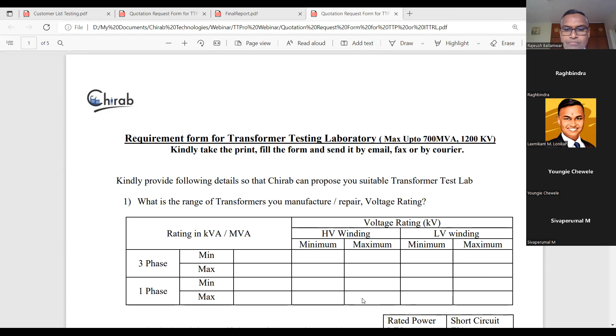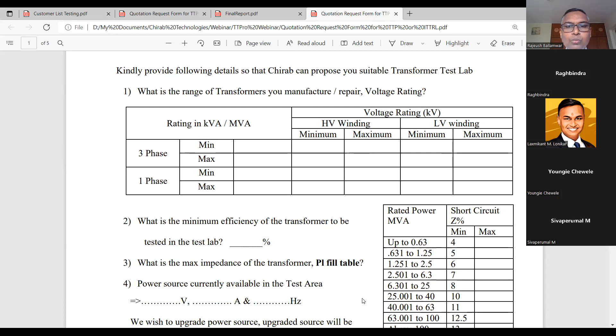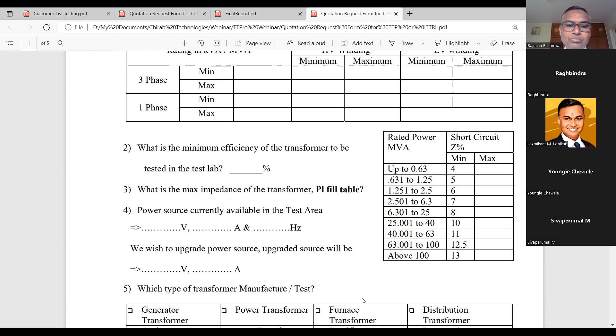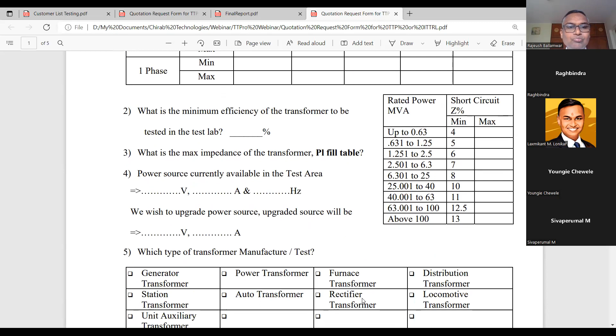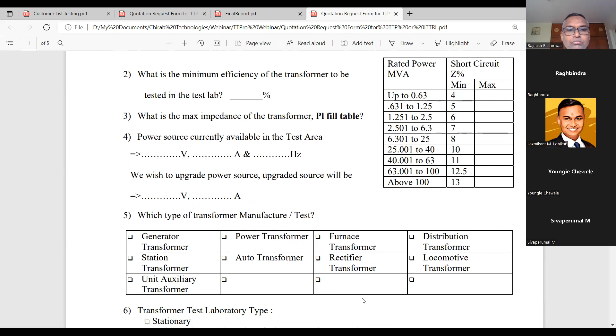Here you have to mention data like the range of transformer. As you know, this transformer test laboratory is suitable for single phase as well as three phase. You have to mention only kVA or MVA rating, voltage rating HV as well as LV, efficiency data, and impedance of the transformers in tabular form. Also mention whether you have a power source currently available, its voltage rating, current, frequency, or whether you need to upgrade the power source, giving the required voltage and current rating.